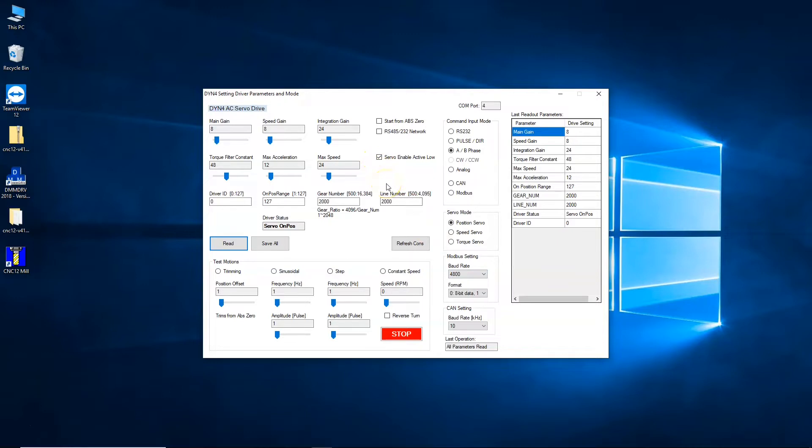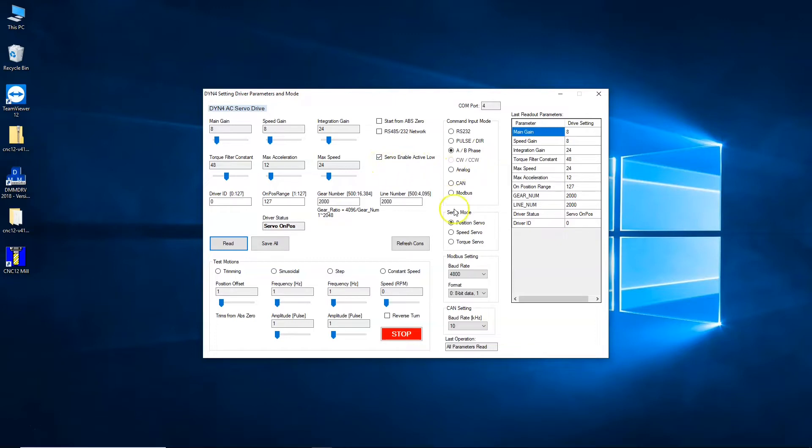I'm going to go from the document that DMM sends out. There is a video I'll put a link in the description below. Set DYN4 servo drive enable logic to active low, and I've already got that checked. Set DYN4 drive into position servo mode. It's already in position servo mode. This is a working drive - normally it'll come defaulted to RS-232 with this box unchecked.